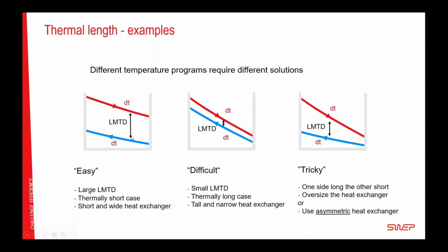That is, if this difference is large, we call it a thermally short case. So not so much heat transfer is needed. A short and wide heat exchanger that doesn't give so much pressure drop is the typical choice here. When the temperatures get closer and closer, the LMTD gets smaller. This is a thermally long case, and to be able to squeeze out all this required energy, a tall and narrow heat exchanger is required, but this will cost more pressure drop. So you will have to be willing to pay more pressure drop for this kind of case than that one.